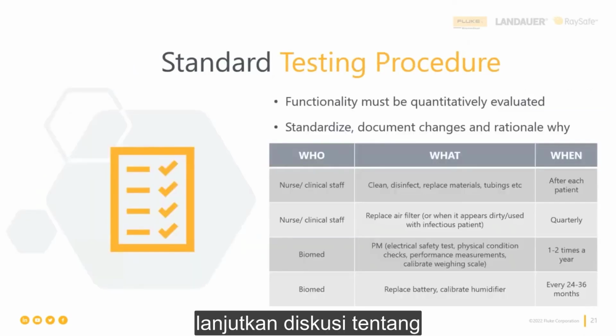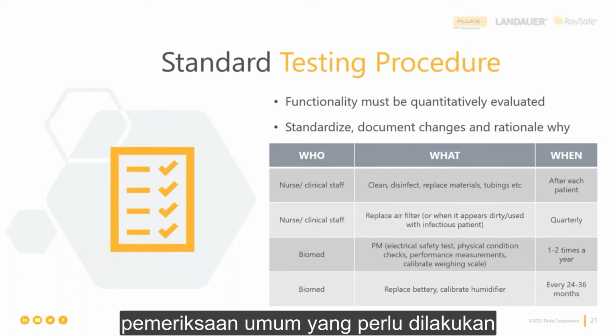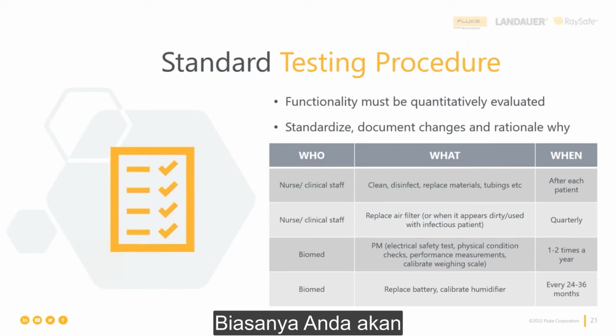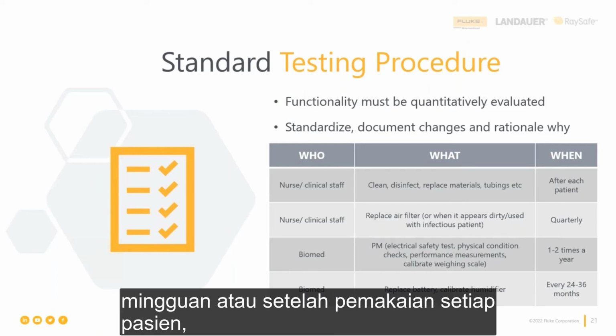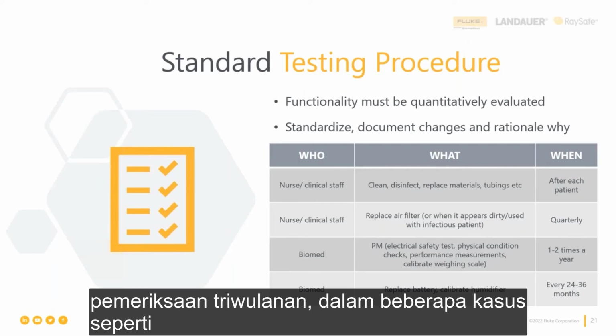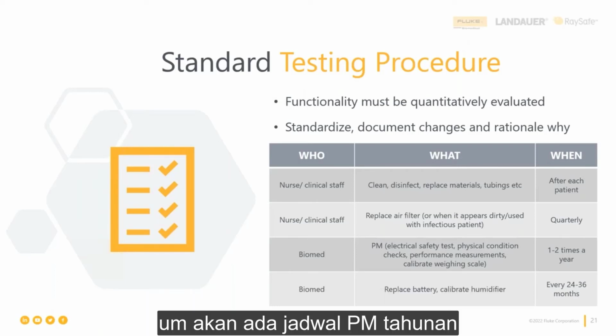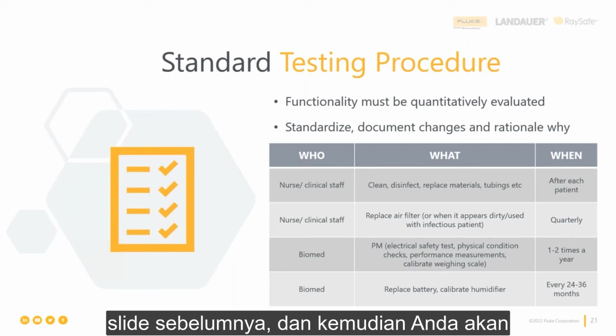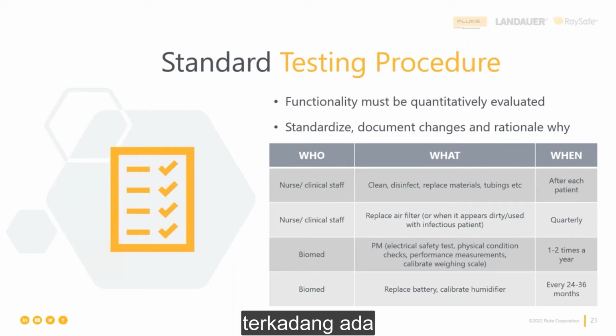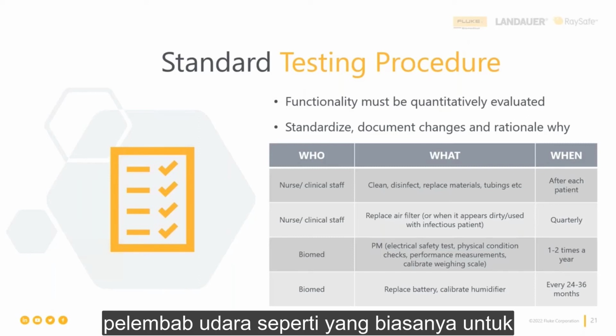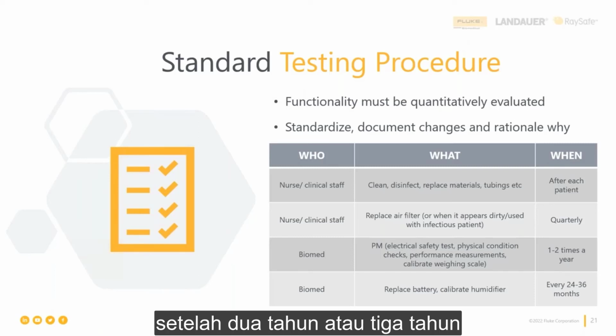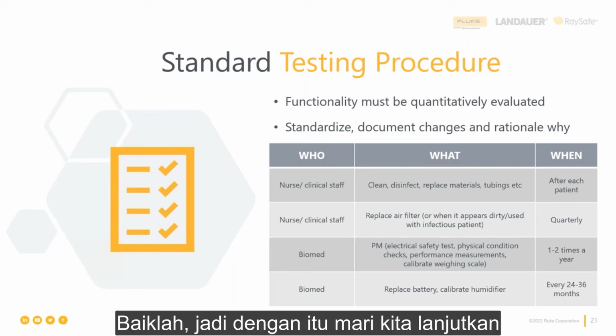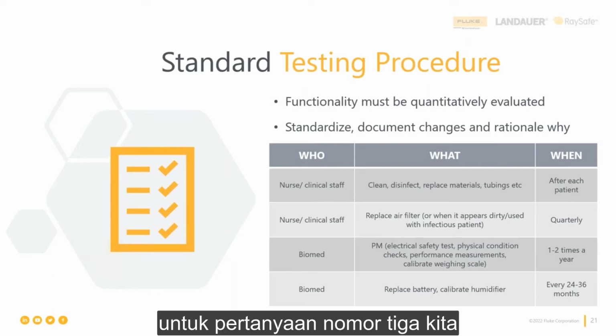Let's switch on to the next slide and continue the discussion of the inspection frequency. So here we have an outline of the typical checks that need to be performed on an infant incubator. Usually you will do all of that performance inspection per the standards and/or the manufacturer's recommendations. These checks will often include either weekly or after each patient checks, quarterly checks in some cases, like for example replacing air filters. There will be those annual PM schedules that we talked about in the previous slide, and then you will oftentimes have the battery replacement and calibrating the humidifier. Those typically come at the 2-year or 3-year mark, which are also important to do. All right, so with that, let's switch on to our poll question number 3.